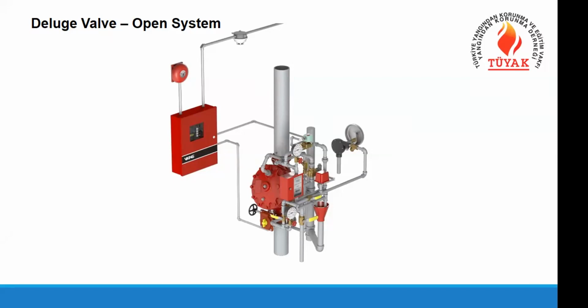There we have an electrical activation panel, and we have a detector system. Electronic detectors like smoke detectors, flame detectors, or other kinds of fire detectors are connected to the activation panel. Here you see the fire extinguishing panel. The panel activates when you have a fire alarm. The panel activates a 24-volt solenoid that releases the pressure inside the valve and opens it and sends the water to the pipes. And this system also has no water inside the pipes, but also no pressurized air inside the pipe. It's completely open. So it's a different kind of system that I will show you in a foam system example in coming slides.